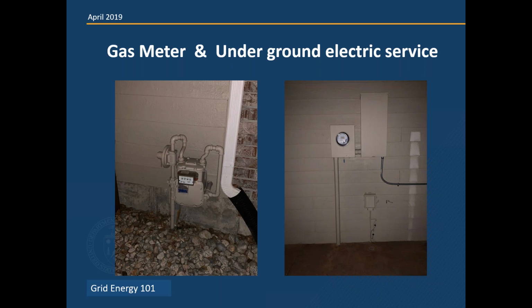I had a discussion with the neighbor there in Colorado. I said, hey, what if that piece of wire from your meter to the transformer has a fault or has a problem? It's not the utility's job to replace that. It's the customer's, because the utility stops at the transformer. And they go, wow, I wish I'd have thought about that before I put all that concrete in. Anyway, next slide, please.